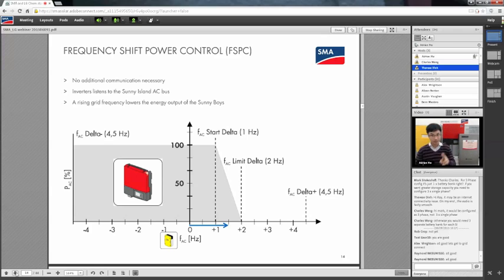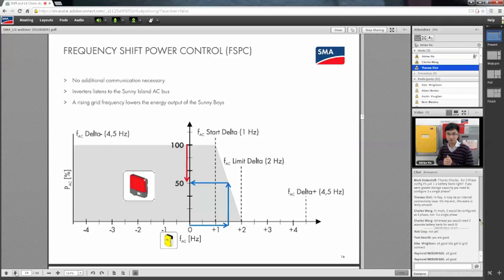The Sunny Island will sense this surplus of power and increase the frequency of the grid it's making, from 50 hertz up to, in our case, 51.5 hertz. The Sunny Boys, the red box, in off-grid mode, will see this increase in frequency and drop their power output. For our example, 51.5 hertz AC corresponds to a 50% AC power drop - so if it's generating 5 kilowatts, it will be throttled down to 2.5 kilowatts or lower.